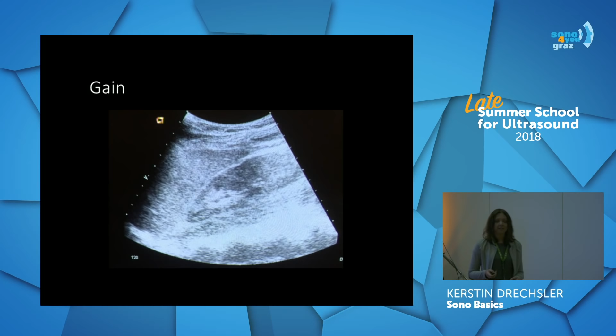The same applies basically to sonography. If we are turning up the gain, so the overall brightness of the picture, we will eventually encounter a picture like that. It will be blurred and distorted, just because the gain is too high. The contrast will be really, really bad. So we have to adjust the gain. And the same thing is if someone enters the room and turns down the volume: at one moment you won't be able to get what they're talking about anymore, just because it's too silent. The same applies with gain. If we're putting the gain down too much, we just won't be able to see anything.